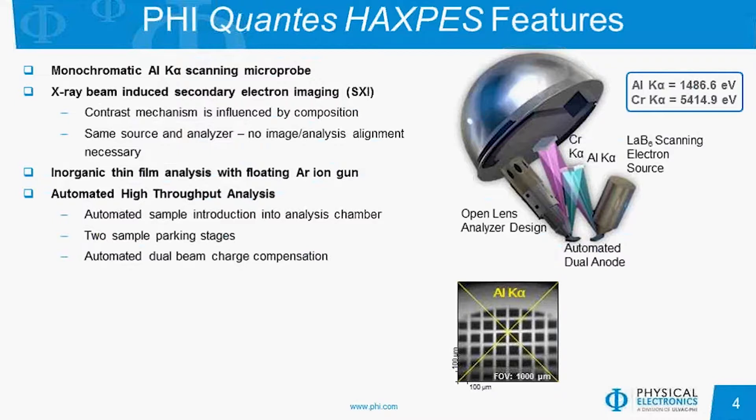Both the Quantera II and the new QUANTES instrument use PHI's scanning microprobe technology, where a focused electron beam generates a focused X-ray beam. Using this scanning microprobe, we are able to generate X-ray-induced secondary electron images, also called SXIs. For example, I have shown an SXI of a copper TEM grid taken with the aluminum K-alpha source. These images are generated with the same X-ray source and analyzer used during XPS data acquisition, so no additional image and analysis position alignment is needed. The contrast mechanism in an SXI is mainly dependent on photoelectron yield, meaning different chemical environments, making SXIs useful for finding defects or verifying sample uniformity.